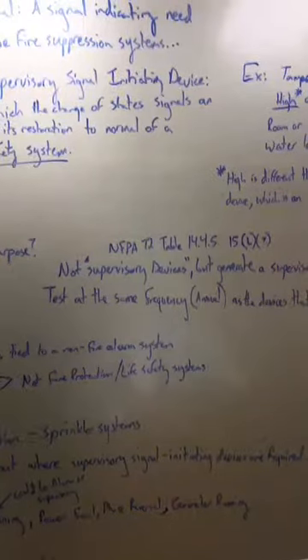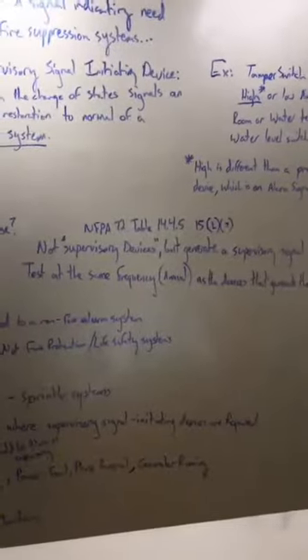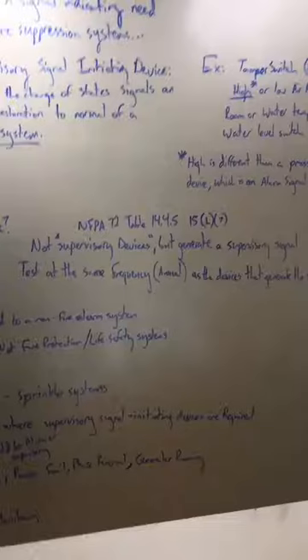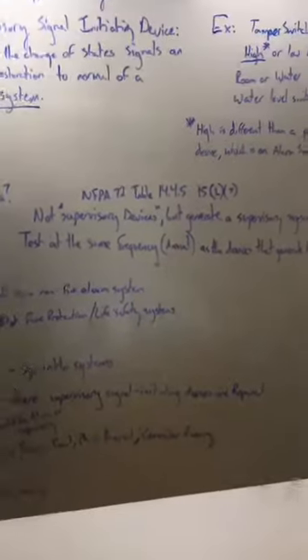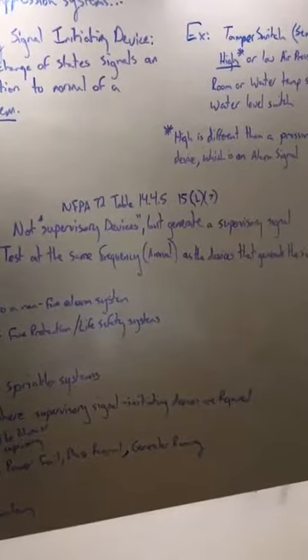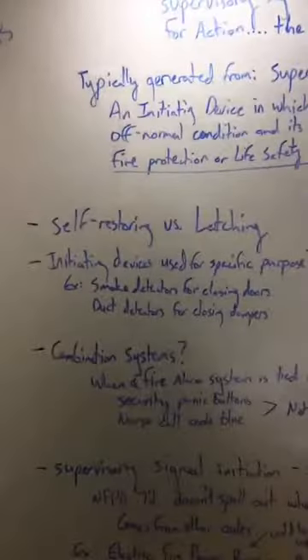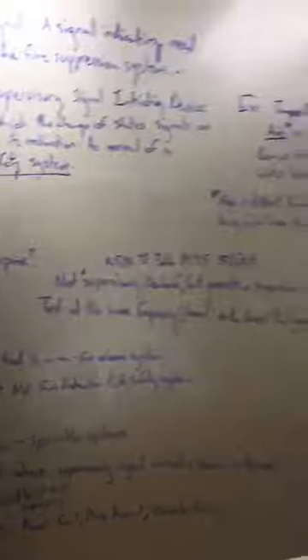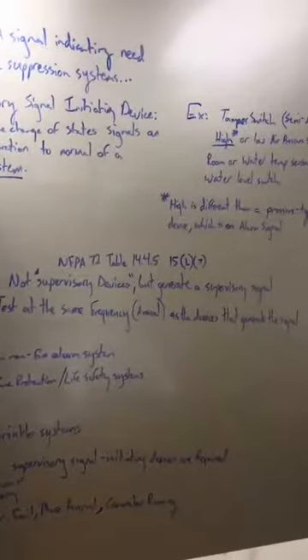These are not supervisory devices. They just generate a supervisory signal. So they are tested at the same frequency annually as the devices that generate the signal. So smoke detectors are required to be tested annually, so the signal associated with it is required to be tested annually. Even though it produces a supervisory signal, it's not required to be tested quarterly.